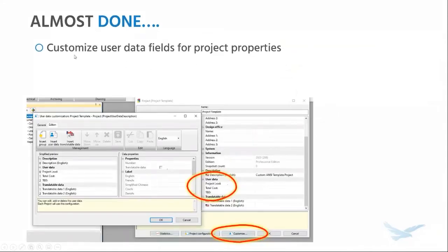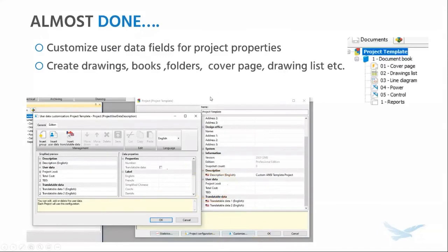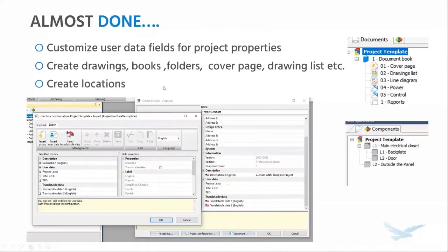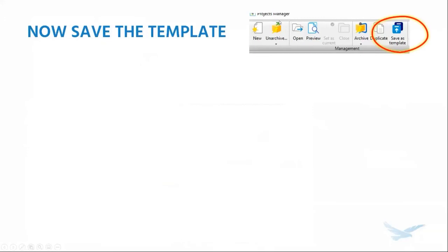Almost done. Let's take a look at what else we can do to our projects — namely, customizing the user data fields of the project properties. If all your new projects need to have some custom properties, might as well go ahead and do it at this point. Go ahead and create any empty drawings, cover pages, drawing list reports, or even some book and folder structures you would like to see in all your new projects. If you need to draw wires — for example, if all your new projects need to have main power coming in — might as well draw that in. Create locations and sub-locations that you want to see in your new projects. Now that you've got your empty project looking exactly the way you want it, go ahead and save it as a template in the project manager — this template will now be used to create your new projects.